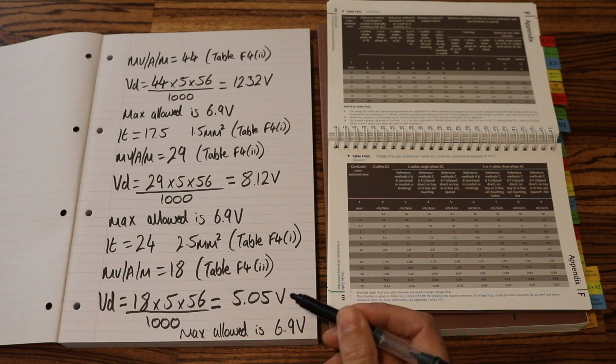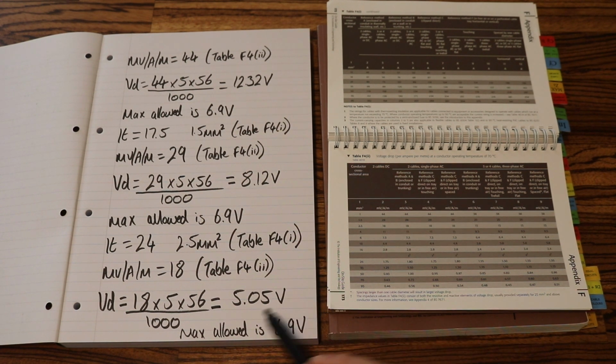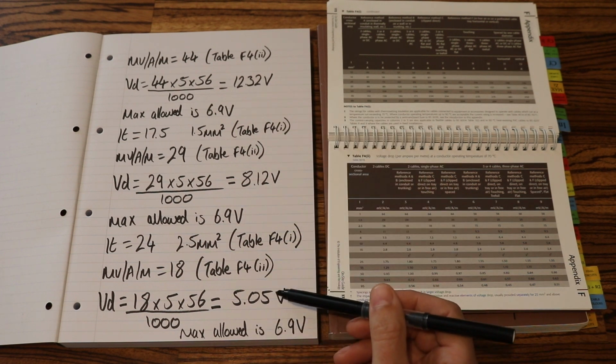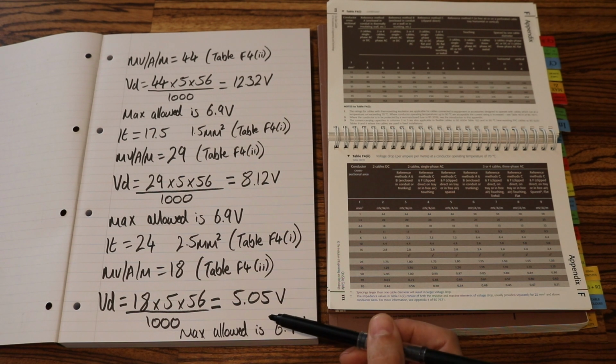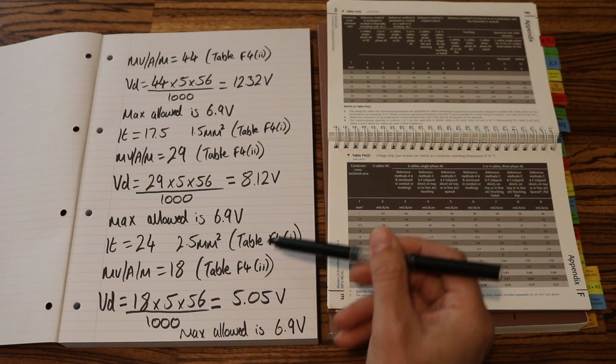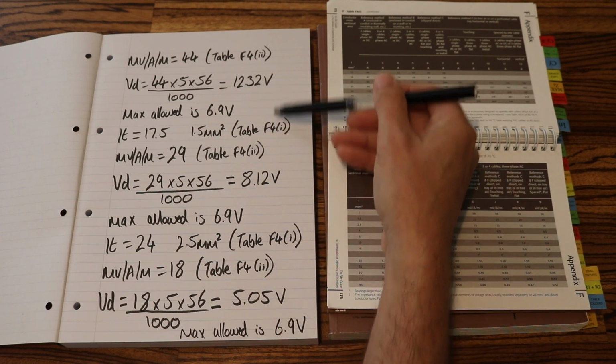So, it's a little bit of a long-winded process, but we're showing the examiner that we know what our maximum allowed is at each step. This shows him that we understand what this volt drop value means, and we always make sure, I know it's a little bit laborious, but we do it every single time, reference every single table that we use. But we finally found our volt drop. So we are now at the correct size cable, which was 2.5.